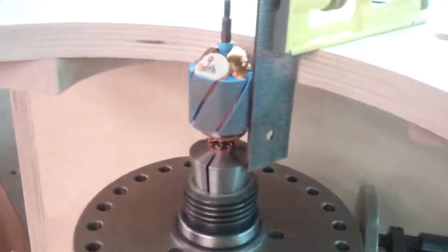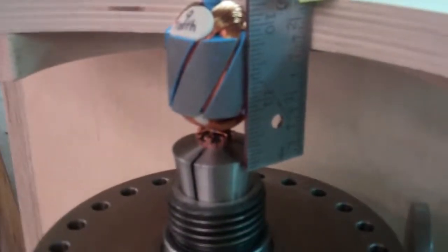And again, this is starting on zero. And this is a seven pole armature. And it has a full pole of skew built into the armature, which is 51.4 degrees. That's one seventh of a circle.